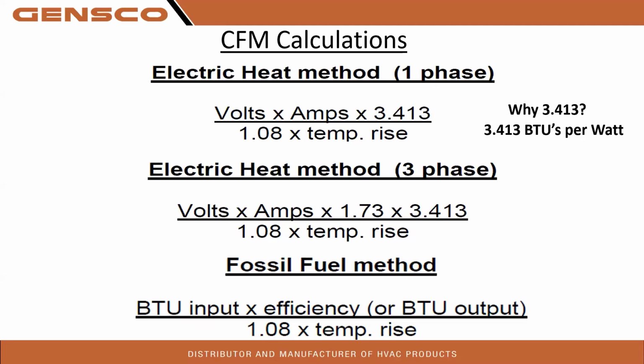Yes, for sure, Mark. Yeah, when you're doing this with an air handler and you're trying to find out whatever CFM you have on a single stage system, most of the compressor blower speeds are the same. So what you're going to want to do is turn up the heat and take off any lockouts so that your electric backup heat comes on when you're running at the compressor fan speed. And then just go outside or pull the contactor so the compressor doesn't run. So it runs at compressor fan speed, and then you have all your strip heat come on. Then you take your temperature rise with that, without the compressor running, right? And then figure out your calculation at that. That's the only comment I wanted to make.